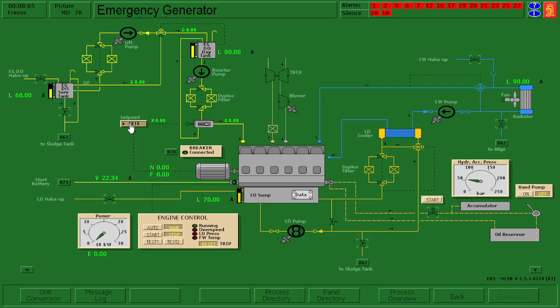When you push more fuel in there, you're wanting the thing to spin faster, right? And that would raise your frequency, and you wouldn't really have much of an effect here on the wattage output. You'd just be increasing the frequency. But when you have the excitation voltage, which puts your counteracting magnetic field on this generator to keep you at that fixed 1800 RPM, that extra force, like when you try to push two magnets together, that force is what induces the power current itself, your amp output available to you.